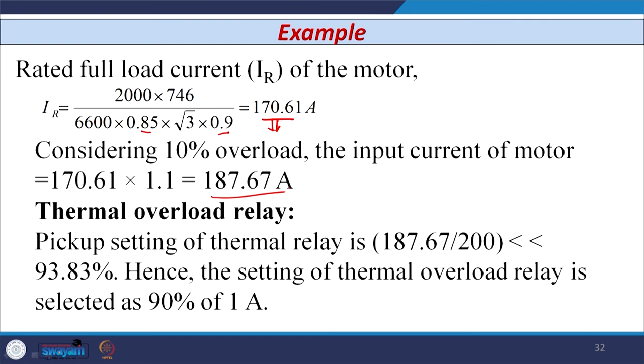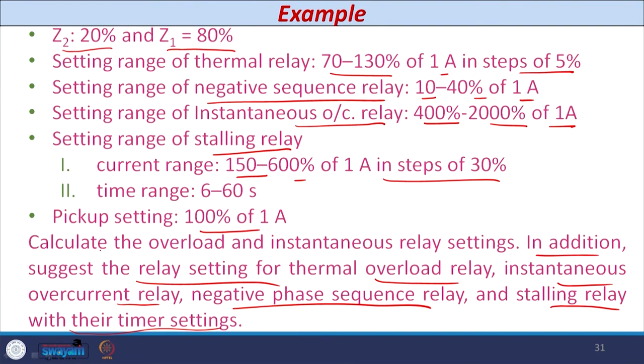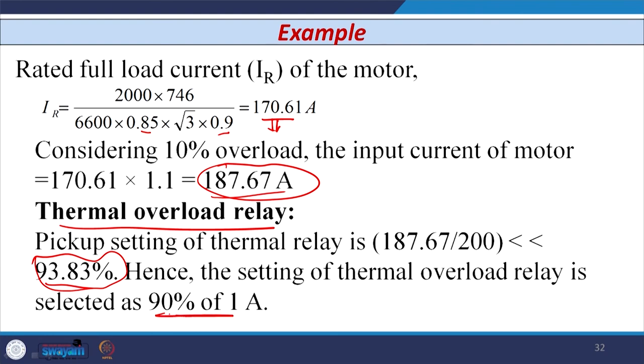For the thermal overload relay, the pickup setting is calculated by converting the overload current to the CT secondary. Using CT ratio 200/1 A, the value comes out to be 93.83% in percentage terms. The thermal relay setting should be below this value. Looking at the thermal setting relay range of 70% to 130% of 1 A in steps of 5%, the next available setting just below 93.83% is 90%. Therefore, the thermal relay setting is set at 90% of 1 A.